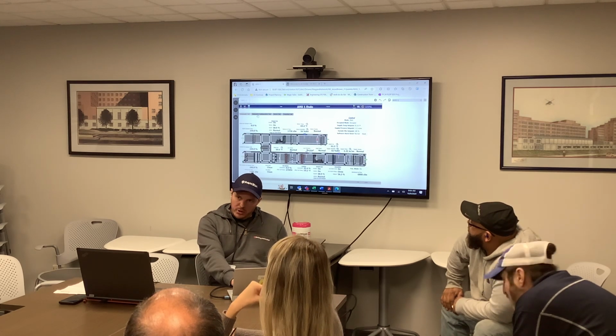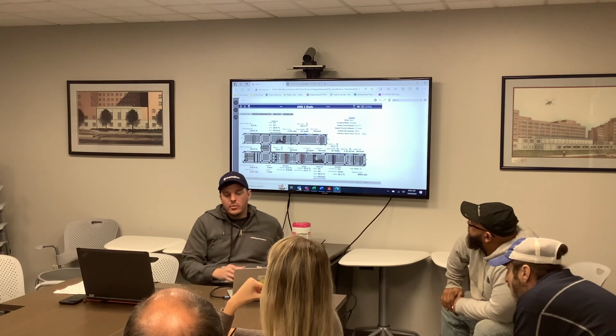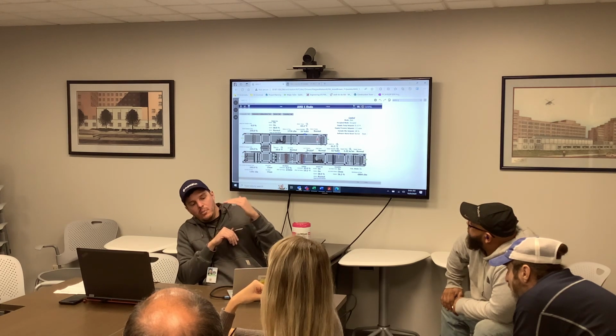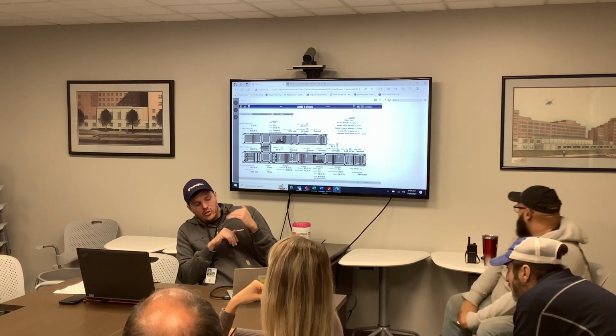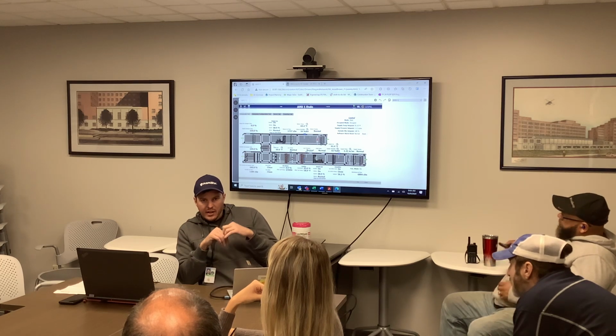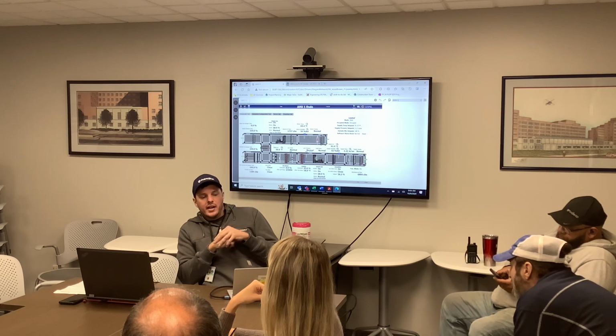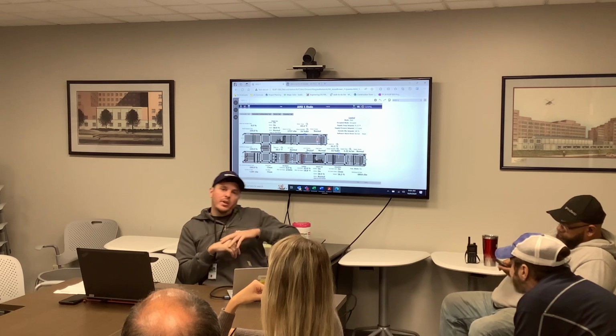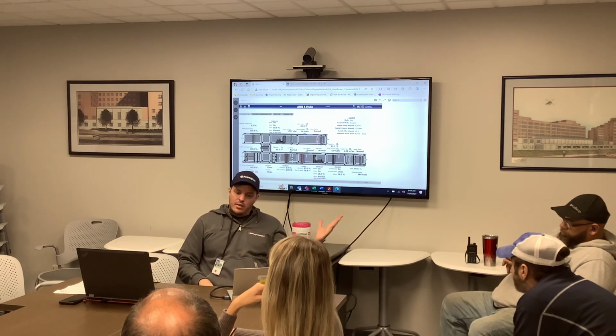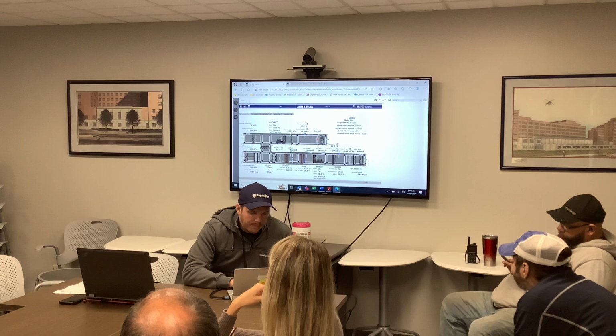There is a trim program in this system that will actually start ramping up that set point if you're not seeing a differential at your VAVs. And as this ramps, we're actually tripping on high static, so above 3 inches. So we can't get the static we need at the trunks.